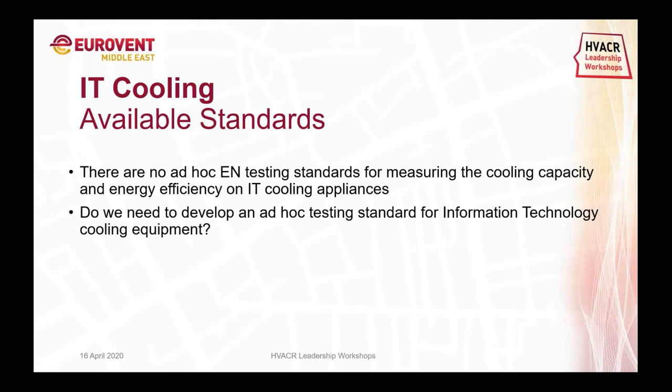Regarding the question on screen — do we need to develop another testing standard for information technology cooling equipment in Europe? My opinion is that we should do something with that. For the moment, we could be testing traditional CRAC and CRAH units with current European standards. But newest products taking benefit of free cooling or evaporative cooling technologies definitely require new testing standards, including also new testing conditions.